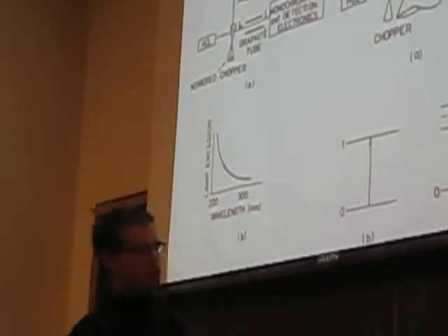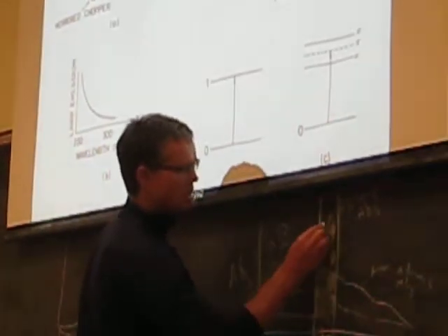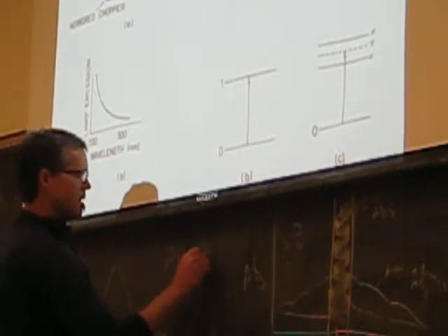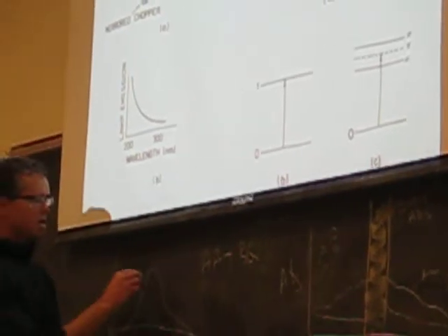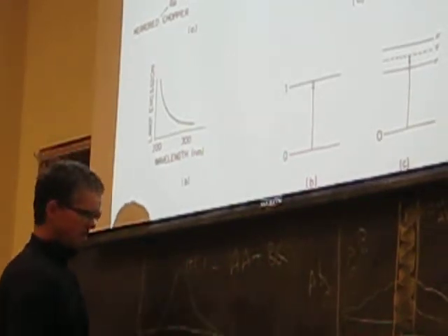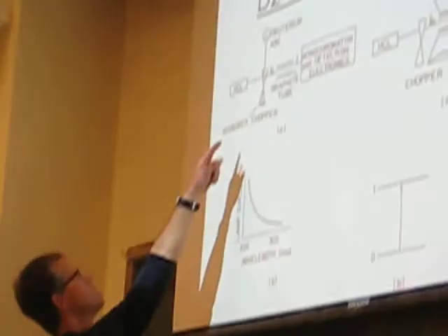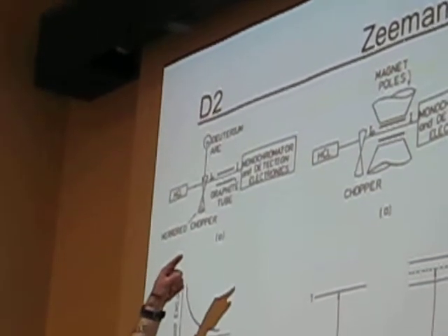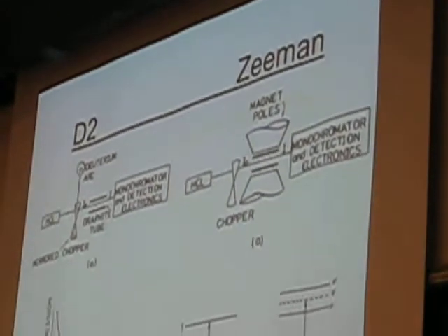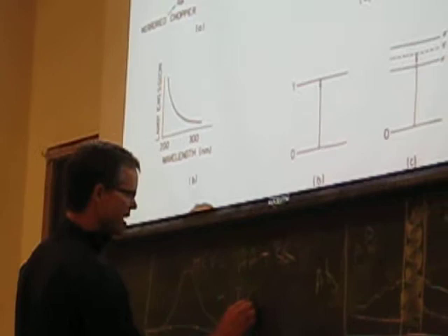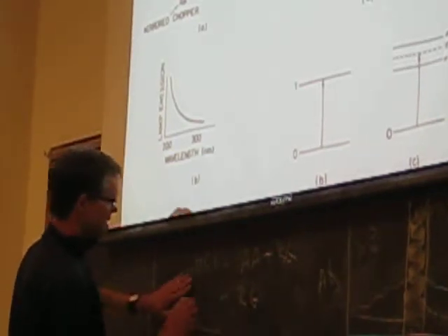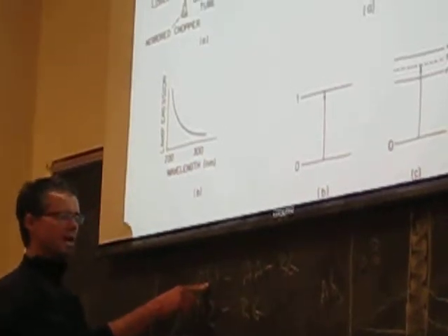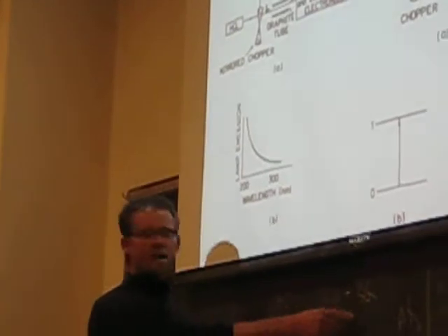And then you should be measuring all this. So that would be atomic absorption plus, I'll call it background, right? So the hollow cathode lamp is measuring that. And then when the mirror is rotating, it would block the hollow cathode lamp and reflect in light from the deuterium arc lamp to pass through the flame, in your case the instrument. And then it would be measuring only background, right? So the D2, the deuterium arc lamp, will be measuring only the background signal. A hollow cathode, when that's going through the sample, will be measuring atomic and background signal.